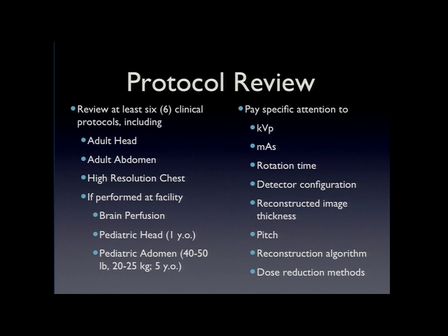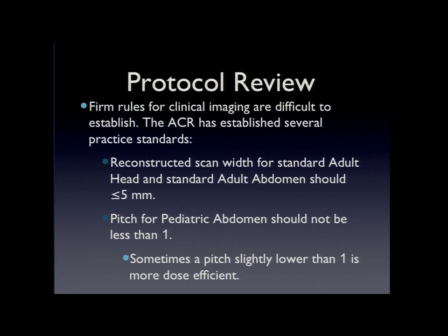And then look at the reconstructed image thickness to see if that's appropriate clinically. Of course, a lot of that is for the technologists and radiologists to deem whether it's clinically relevant. Also evaluate the reconstruction algorithms, such as ASIR or IRIS, that are being applied to help minimize dose. Are they being used effectively, and do you have them set up properly? And the dose reduction methods being used, are they being optimized? So you need to look at that and work with that team. You need to have rules to make sure that you maintain these protocols once you establish them.